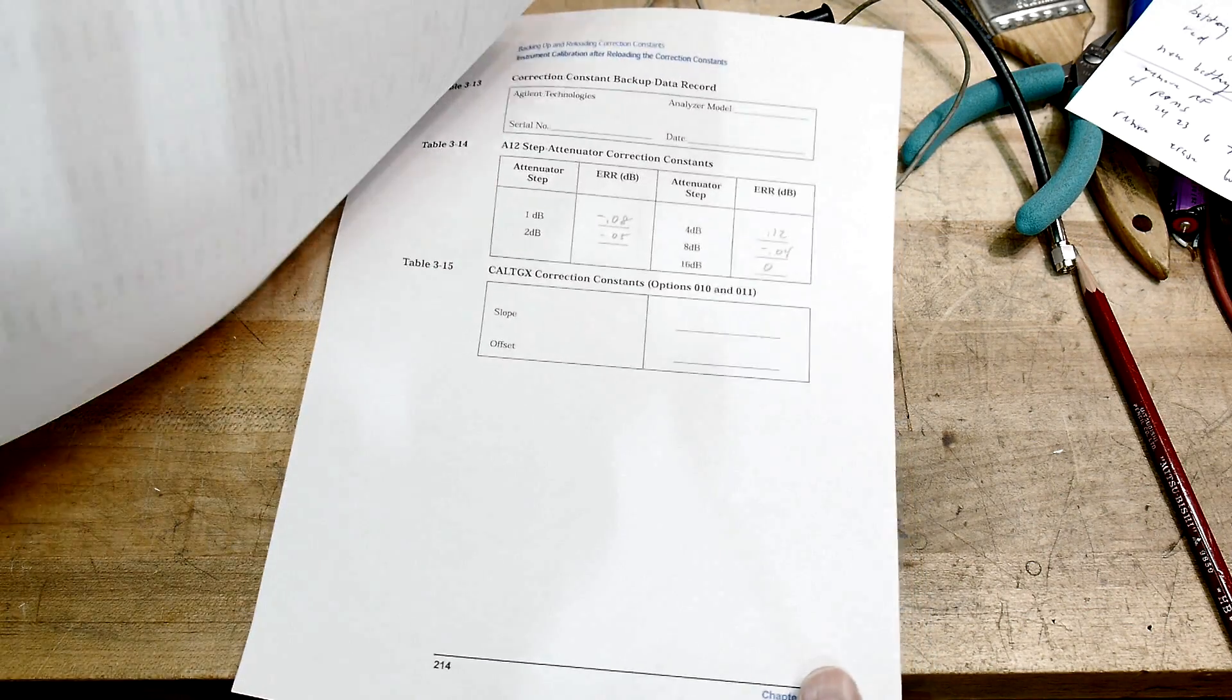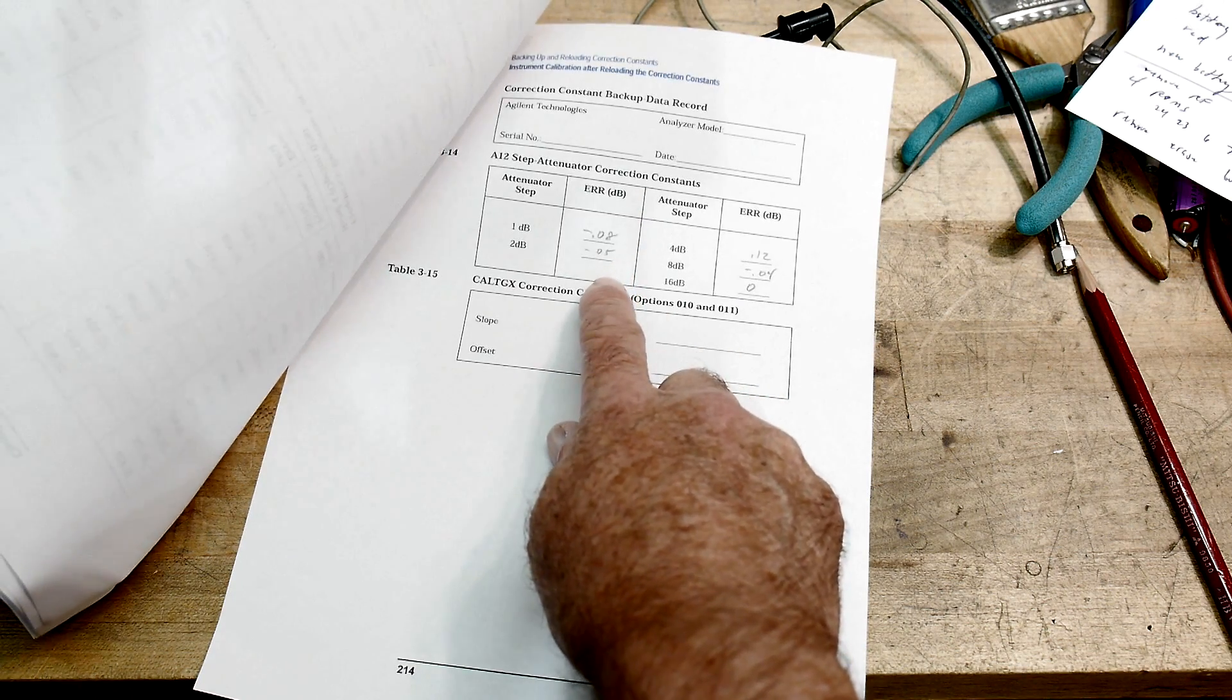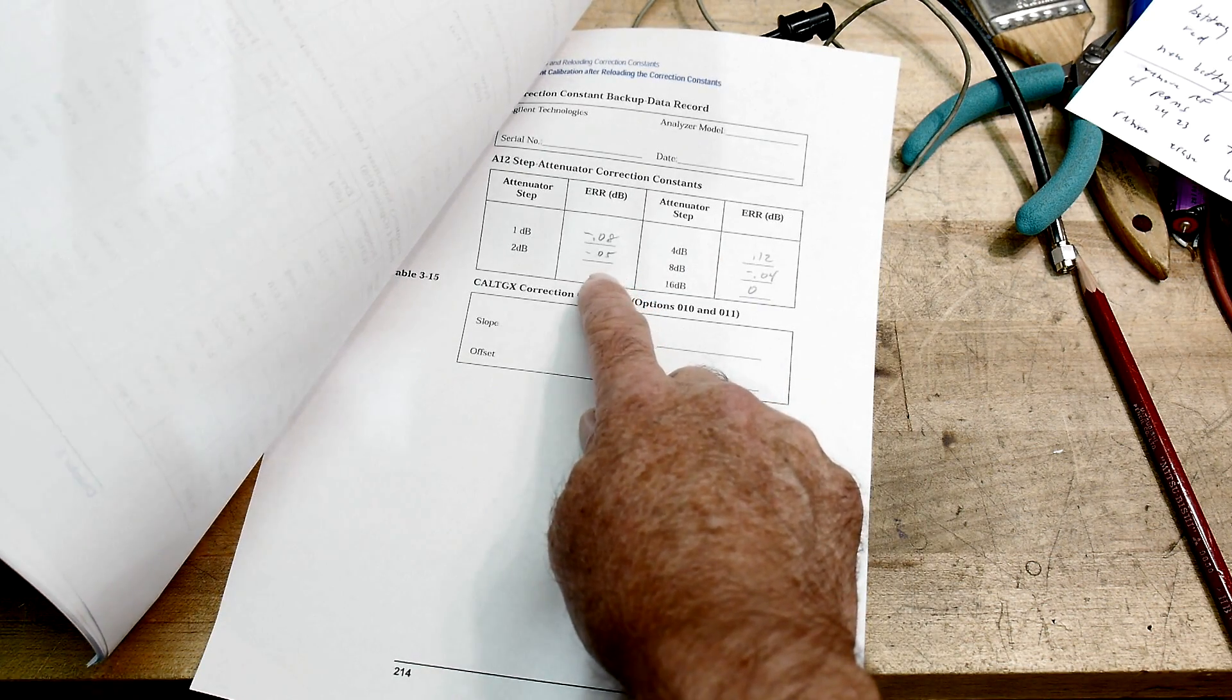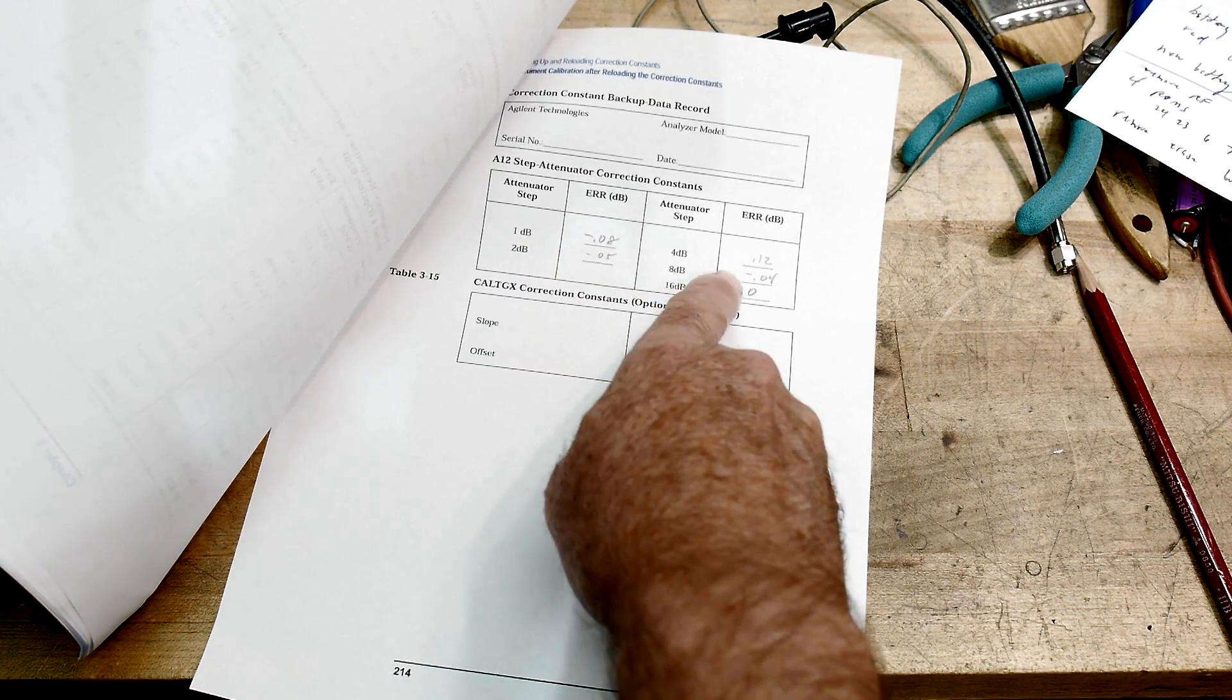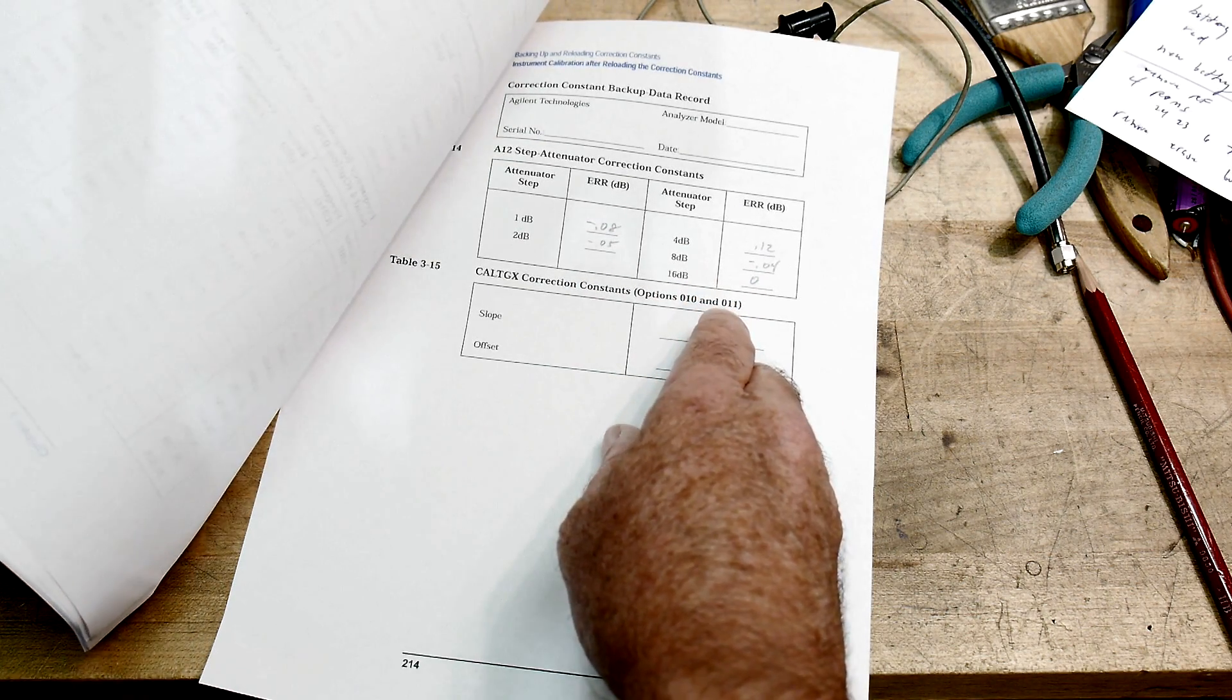And then there's one more table you need to fill out, which is the calibration for the attenuator. There's a mechanical attenuator in there. And there's five steps that you need to have corrections for. And that's done at the factory. So you write those down.